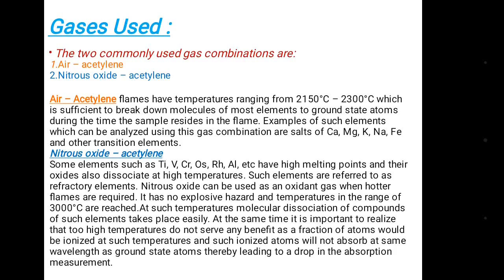For the nitrous oxide-acetylene combination: some elements such as titanium, vanadium, chromium, osmium, and aluminium have high melting points and their oxides also dissociate only at high temperatures. Such elements are referred to as refractory elements. Nitrous oxide can be used as an oxidant gas when hotter flames are required; it has no explosive hazard and temperatures in the range of 3000°C are reached.